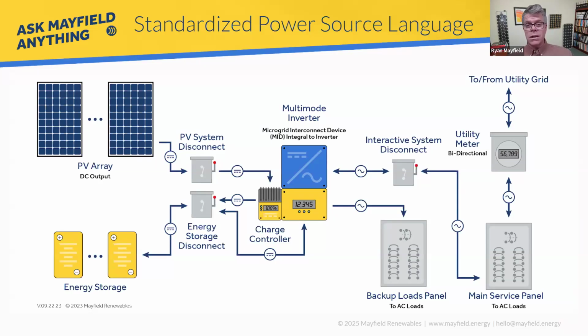If it's not integrated into the inverter or whatever equipment you're building, then you'd have to add an external one, as shown here. There are three ways in 706.15 to meet the disconnecting means for the system: integrated, external, or a situation where you can lock the disconnect depending on its location.